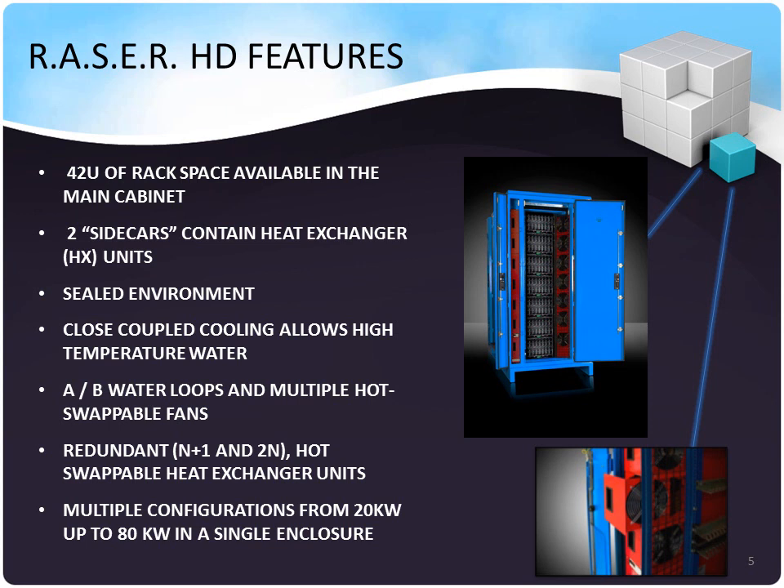Thanks, Tony. This is Simon Rorick here to talk to you about the R.A.S.E.R. HD and some of the features we bring to the table with this new product. It has 42U of very deep rack space available in the main cabinet. On each side are two sidecars containing heat exchangers. It has a sealed environment. Close coupled cooling allows for high-temperature water cooling strategies. Each heat exchanger has an A and B water loop and multiple hot-swappable fans to meet Tier IV data center infrastructure requirements.